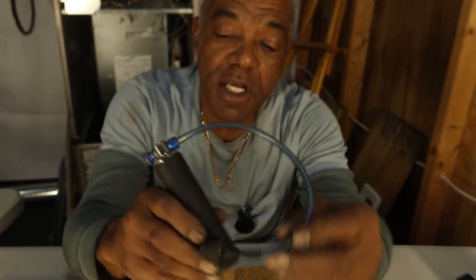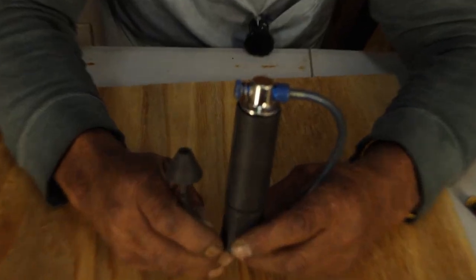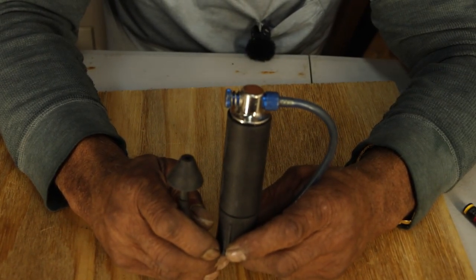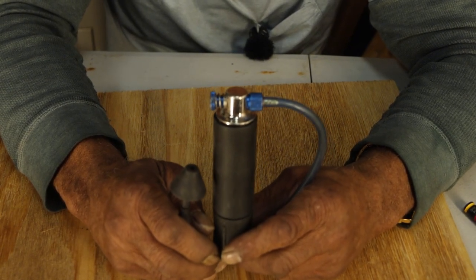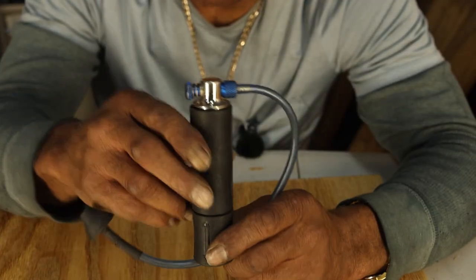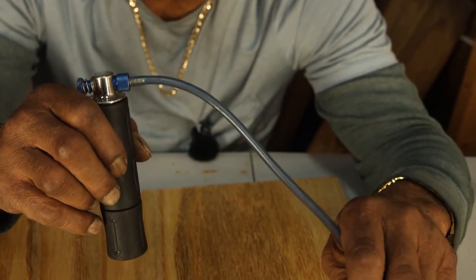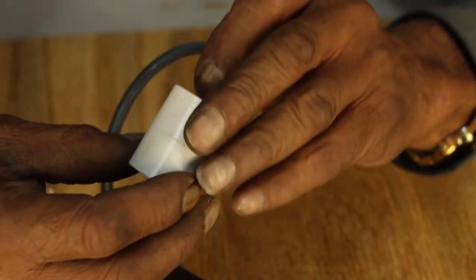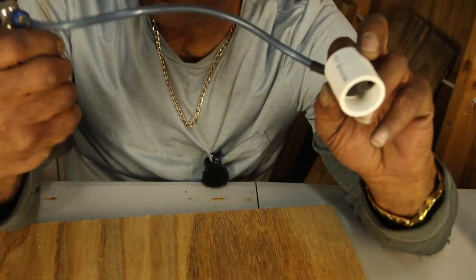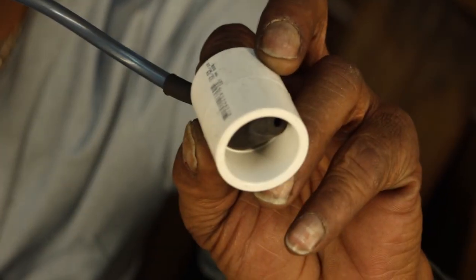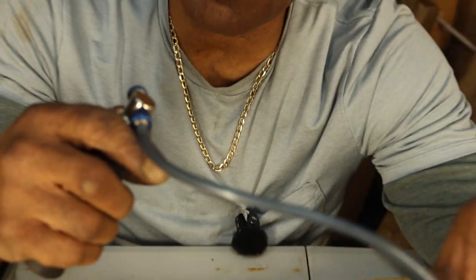This is a swoosh kit. It's used to blow out condensate drain leaks. Sometimes the condensate drain line just gets full of trash and gook that accumulated in the unit. It clogs the line up, causes the system to leak water, flood the basement, and often what we use is a swoosh kit. The way it works is you push this into the PVC. Here's a coupling which is bigger than the actual PVC, so this kind of goes in. But you put it into the PVC, and then when you push the air out, it will blow whatever clog is in the unit.